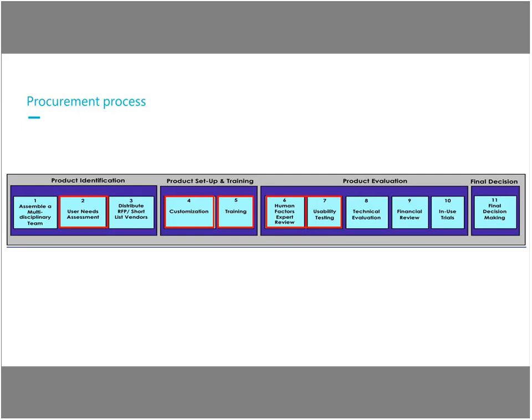Once the organization shortlists several products, then there is some effort required on the part of vendors to help support the usability testing. So what we're aiming for is for people who will come for the usability test to see similar menus, drug libraries, and options enabled and disabled as they would should they purchase the product. So that means that the vendors need to configure their demo versions such that they can support the usability testing, which would be reflective of this specific organization's implementation. So the vendor would create those versions of their demo and provide those.